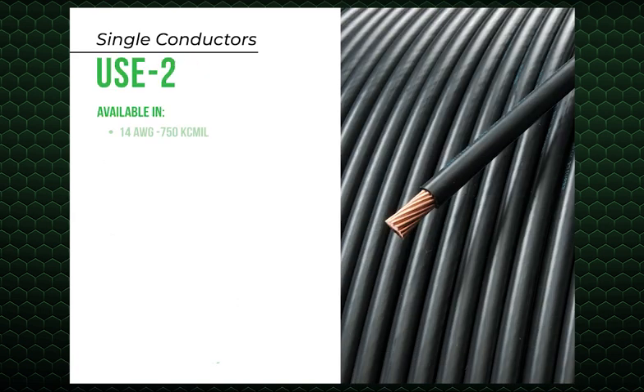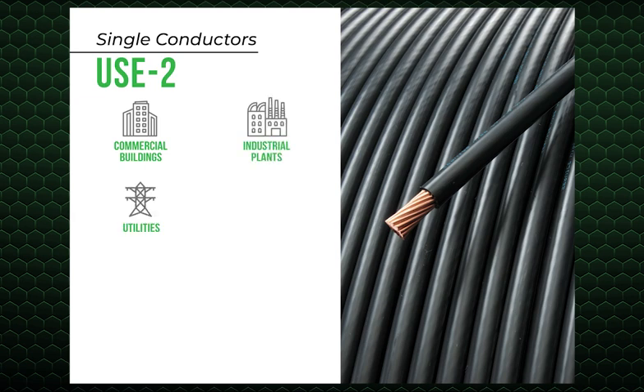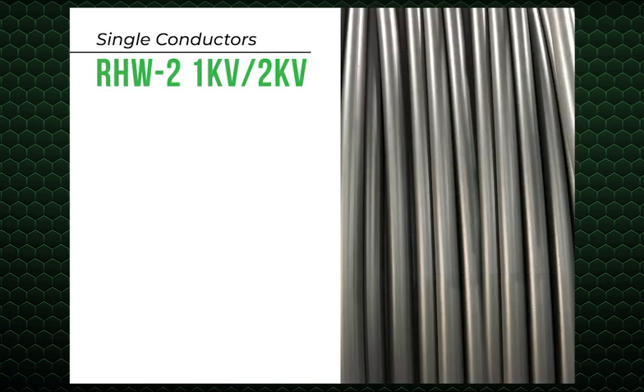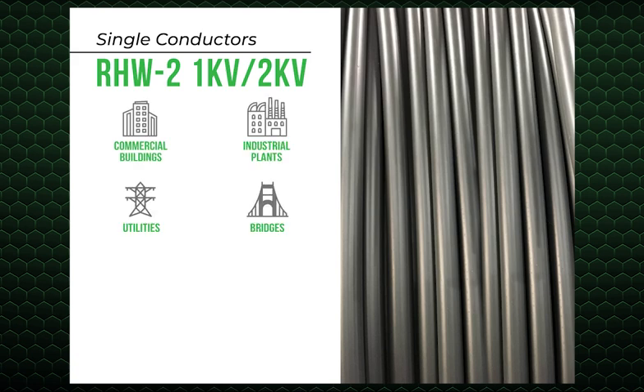USE-2 is available in 14 gauge through 750 kcmil, CT rated, 600 volt/1 kV copper, or VW1 in all industry standard colors. USE is used in general purpose wiring for commercial buildings, industrial plants, utilities, bridges, tunnels, street lighting, and airports. RHW-2 is 1 kV/2 kV rated and available in 14 gauge through 750 kcmil. It is used in general purpose wiring for commercial buildings, industrial plants, utilities, bridges, tunnels, street lighting, and airports.